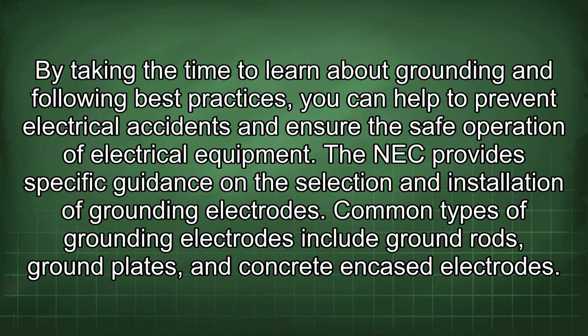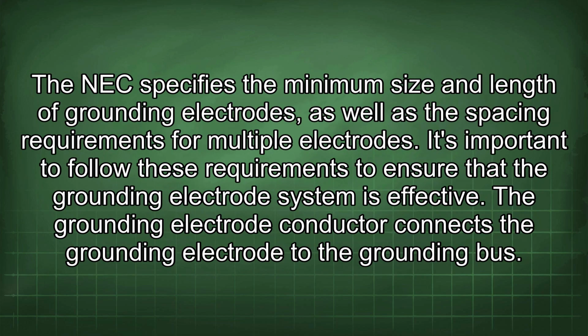The NEC provides specific guidance on the selection and installation of grounding electrodes. Common types of grounding electrodes include ground rods, ground plates, and concrete encased electrodes. The NEC specifies the minimum size and length of grounding electrodes, as well as the spacing requirements for multiple electrodes. It's important to follow these requirements to ensure that the grounding electrode system is effective.